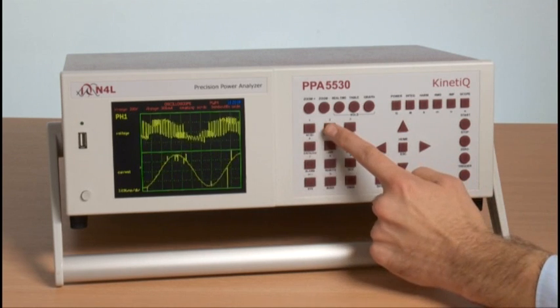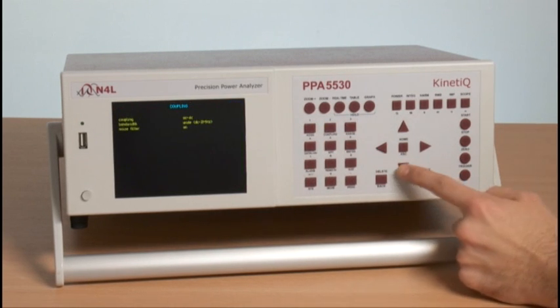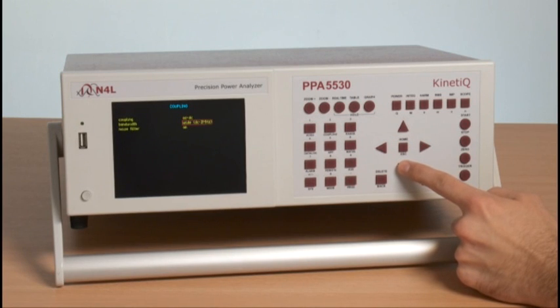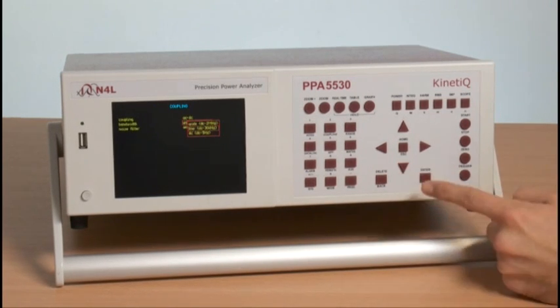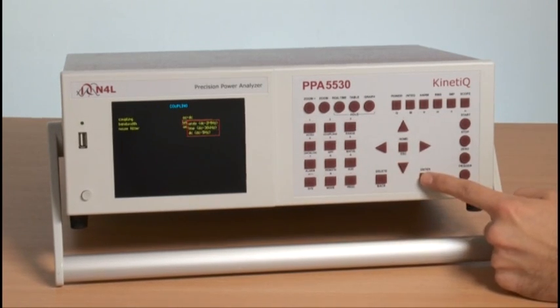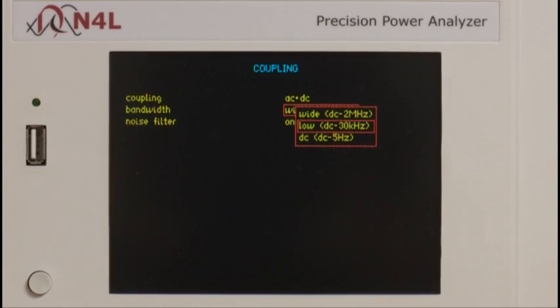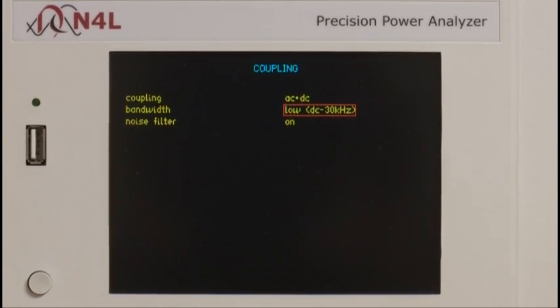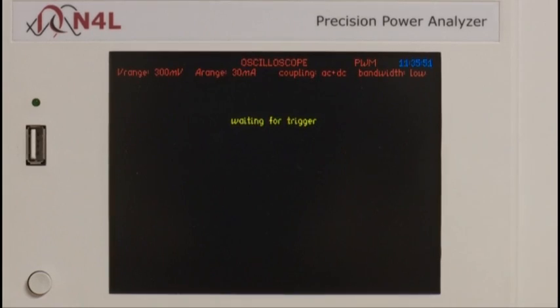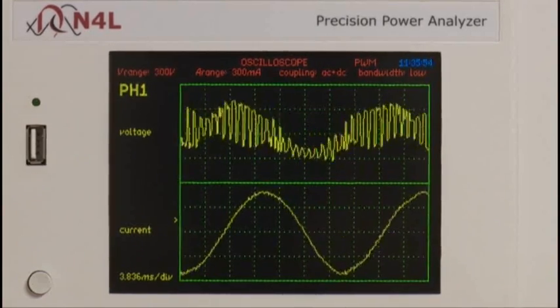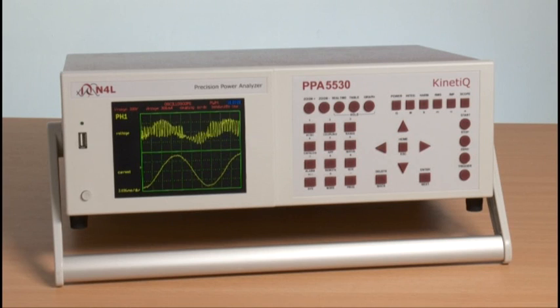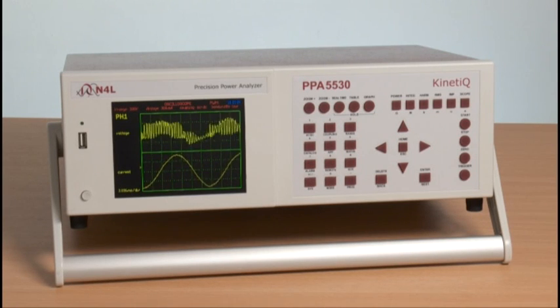In order to solve this problem, it is quite common for measurement instruments to apply a filter that will reduce the carrier and noise. Filtering from around 30 kHz is commonly used for this purpose. By using the bandwidth function, we can apply a 30 kHz filter. We can see that the filter removes much of the noise, resulting in a clean sine wave current, which is going to be easy for frequency detection.